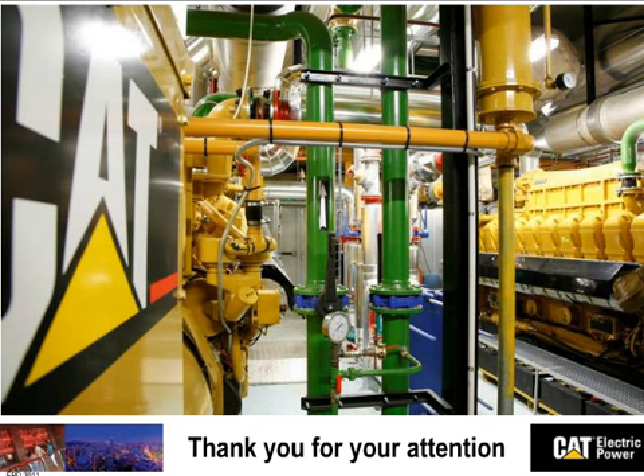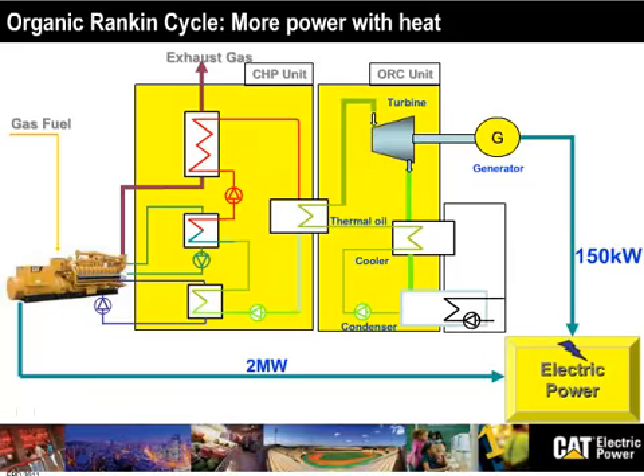Yeah, that's the organic Rankine cycle. Maybe I can bring the slide back because it was not so far. The organic Rankine cycle is just like a combined cycle that is popular on turbines. Here it's performed with the total heat from the genset, the jacket water heat and the exhaust heat, and we actually boil off a fluid which is not water and turbine it into a turbine as a normal combined cycle would do. It's a Rankine cycle, except it's not water. It's an organic fluid or thermal oil. That's why it's called organic Rankine cycle. But you produce extra power by spinning a turbine, a steam turbine. But the steam is not steam. It's a vapor of that thermal oil.